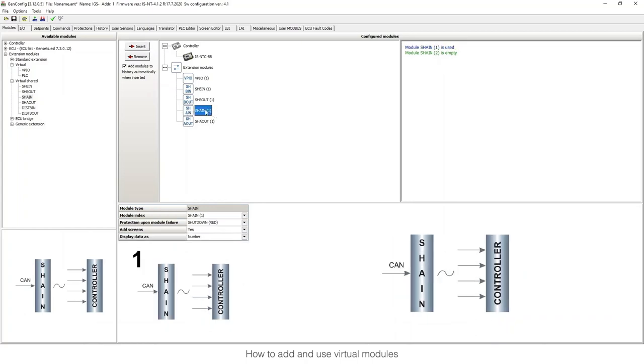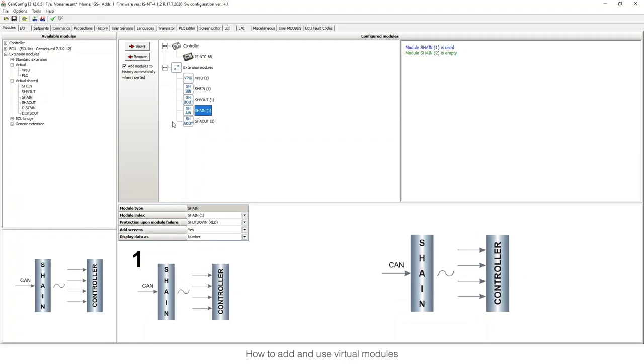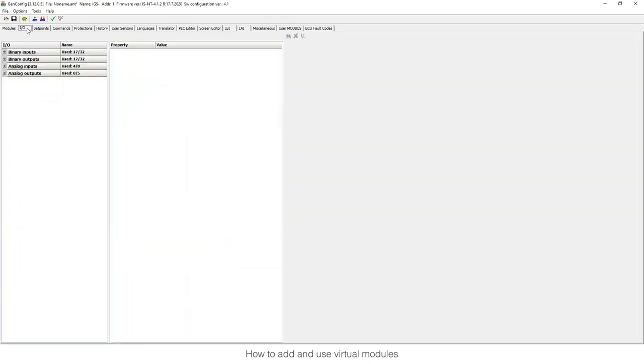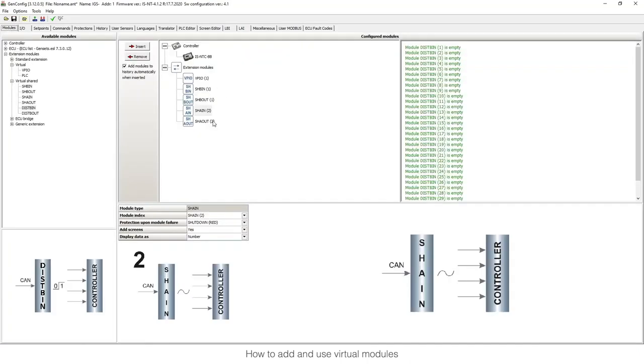There is a limit — a total of two analog inputs and two analog outputs. If you change the index to two on the output side, you also need to change the server analog input to index two in the other controller, so they match. Also importantly, when you go to inputs/outputs for the analog input, you must choose the sensor type 'Electronic' — this is what allows the controller to read the information; without it, you will not read anything.